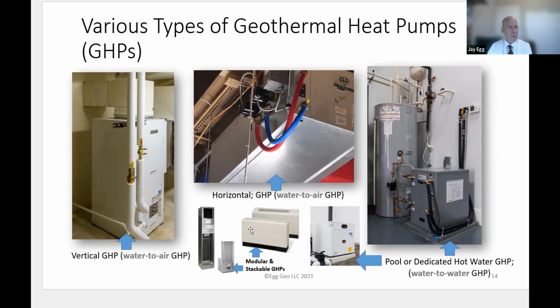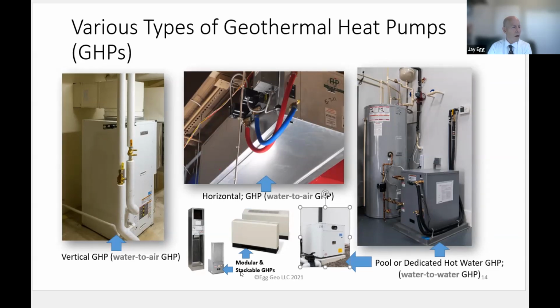And these are also water to air heat pumps, the modular ones like you might see in hotels and apartments, and the vertical stack units like you might see in hotels. Then we get into another type of heat pump that's still geothermal, which is water to water, as it says here. That might include this, which is a domestic hot water dedicated heat pump that makes all the hot water for a building, or a pool heat pump like you see here, which provides all of the heating you might need for a pool in a resort or a home.